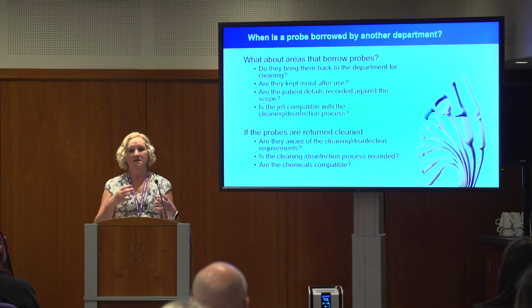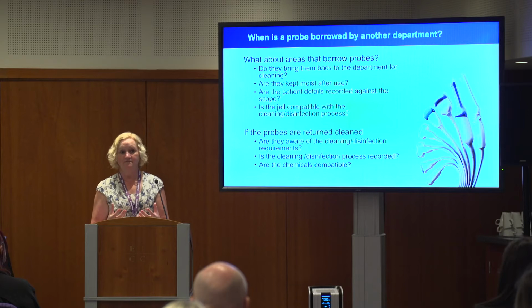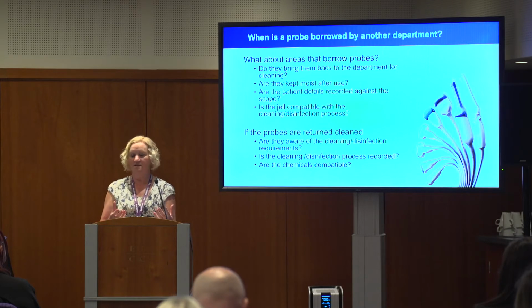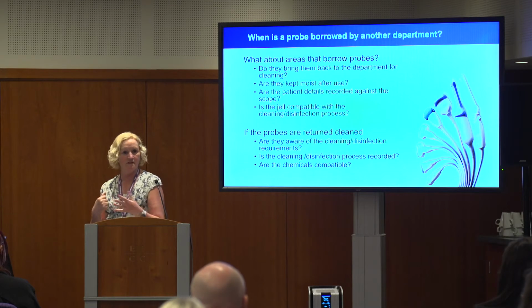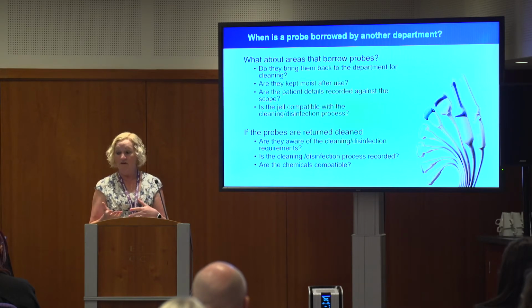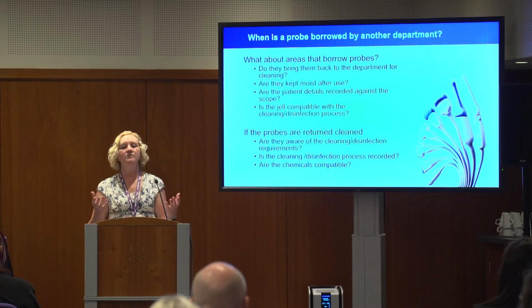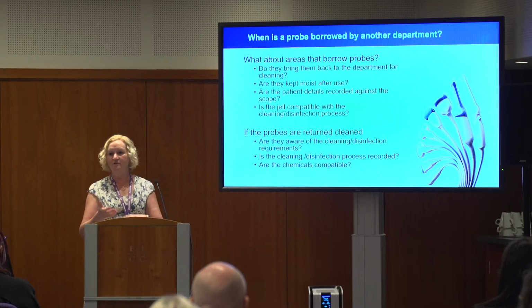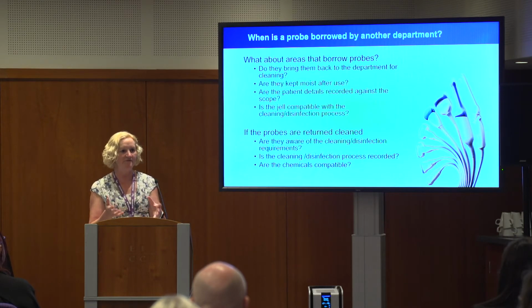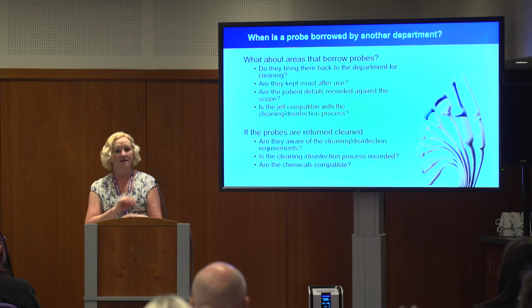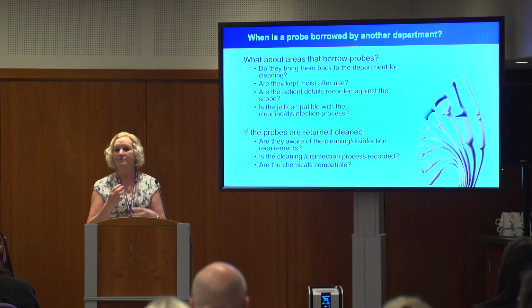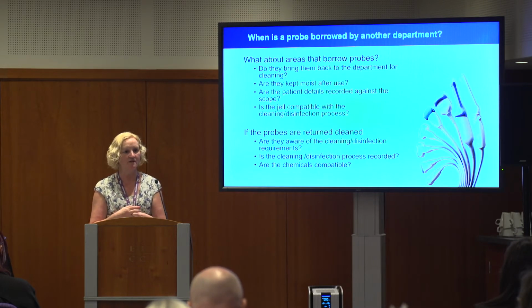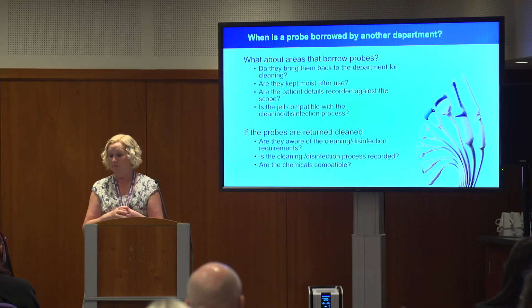So when you're talking about probes that are used elsewhere in the hospital, how do you know they're cleaned? Do they bring them back to your department? They've borrowed one. Do they bring it back clean? Have they recorded it? Are they kept moist? If you keep a probe moist, it's easier to clean. We all know that if you have spaghetti bolognese in the evening and you leave your plate on the side, the next morning it's really difficult to get clean. You've got that sort of orange scum on it. Whereas if you rinse it off that night, you can clean it easily. It's exactly that principle. If you keep it moist, it's easier to remove the dirt and the contamination and the protein that's stuck to the probe.